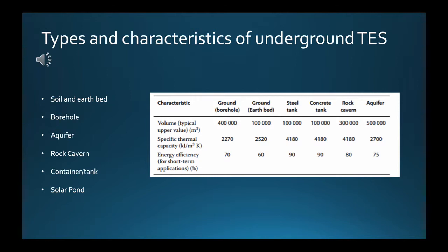A rock cavern can be filled with a storage medium and used as a TES. The storage medium in such systems depends on the ability of the cavern to hold it, and such TES systems are usually large. Containers and tanks filled with a heat storage medium such as water or rock can also act as TES. Container and tank-based TES types can be located in or above ground, but because they are often large and the ground provides insulation, they are often placed underground. Such tanks are often made of steel or concrete because of their physical characteristics, costs, availability, and easy processing, and can be used for new and old buildings.